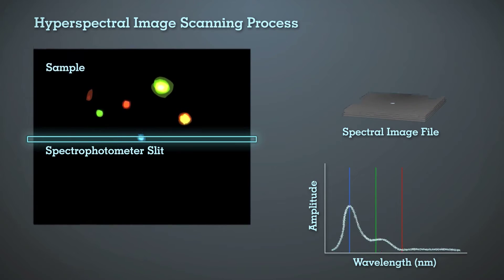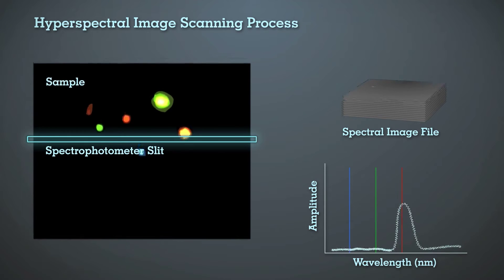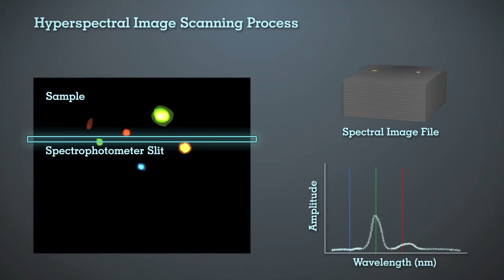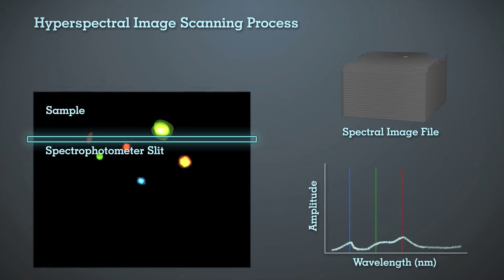The spectrophotometer has an integrated CCD, which collects the sample reflectance spectrum from every pixel of the scanned image. To create a hyperspectral image, the automated microscope stage pushes the sample across the spectrophotometer field of view.